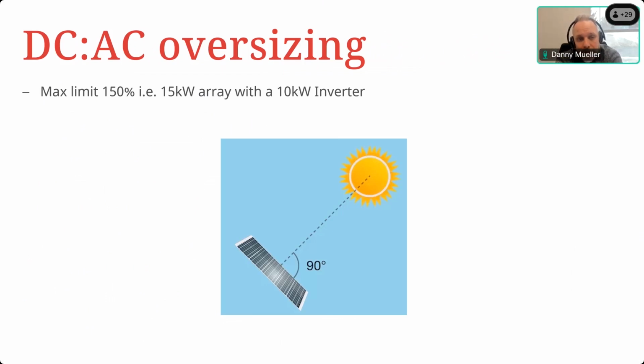You have existing infrastructure on the AC side that you're working with. Generally, you don't want to go above 9.6 kilowatts on a residential project, right? Because you don't want to upgrade your electrical panel. So that 10 kilowatt inverter could technically be derated to 9.6 kilowatts. Yes. And then you can put up to 15 kilowatts of panels on that inverter. So that would make sense, right?